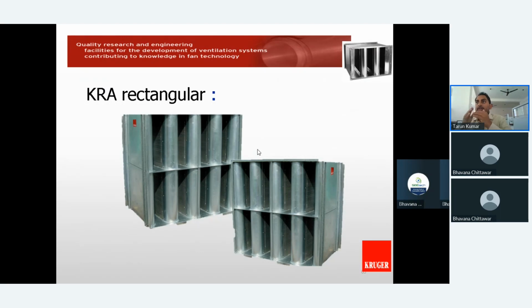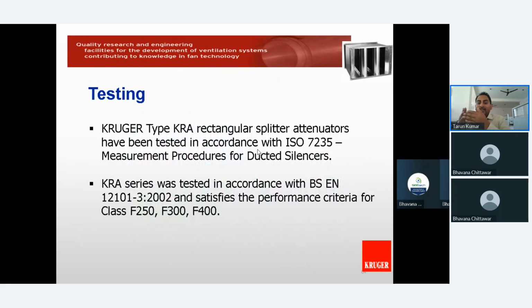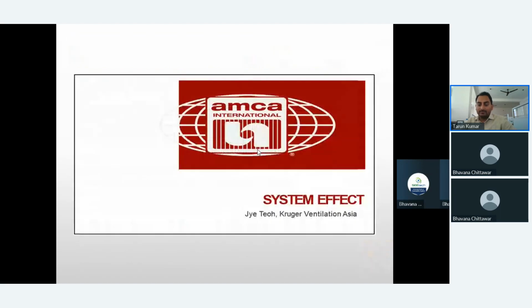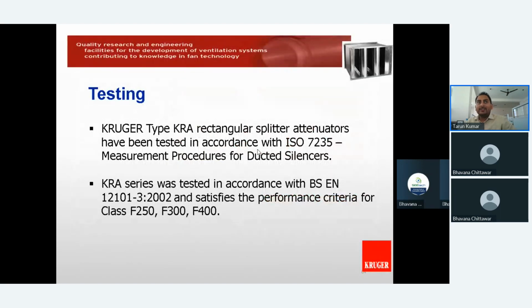So in those kinds of cases, sometimes a sound dB requirement is very mandatory. In that case you can use the KRA attenuator, which has sound reduction of up to 20 dBA as per your requirement, and it is available in different sizes lengthwise and widthwise. It can be modified as per your requirement. This is again tested for fire rating, as well as in accordance with ISO 7235, which will prove that whatever dB we are claiming will be completely achieved by this kind of sound attenuator. So this is all for the ventilation segment.